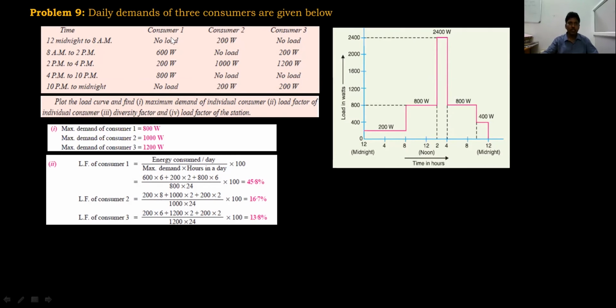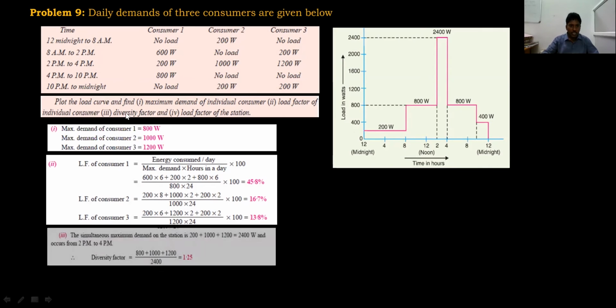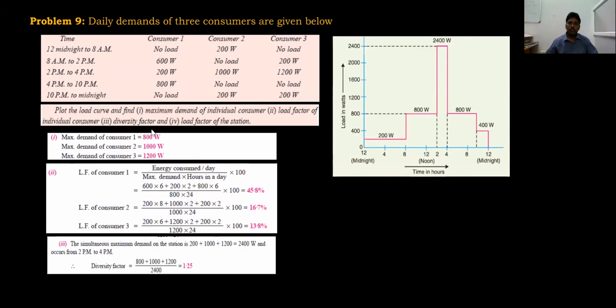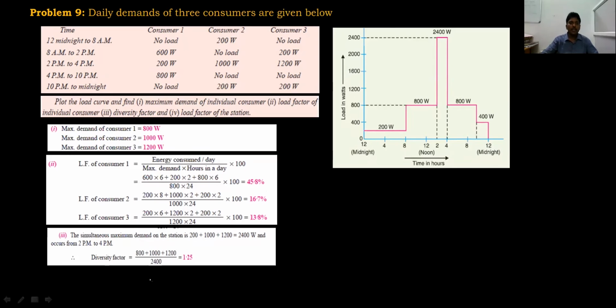And for these three loads, we need to draw a load curve. The load curve is drawn between all these loads. And the third question is diversity factor. Diversity factor is the sum of individual maximum demands divided by the maximum demand on the power station. From the load curve, this is the load curve for the power plant, the power plant has a maximum demand of 2400 watts. Therefore, the maximum demand of the power station is 2400 watts.